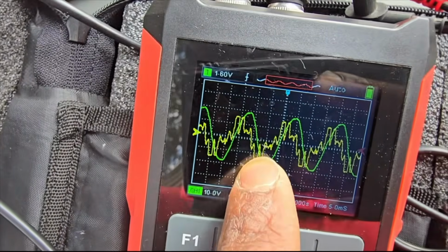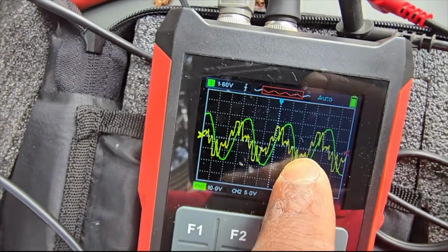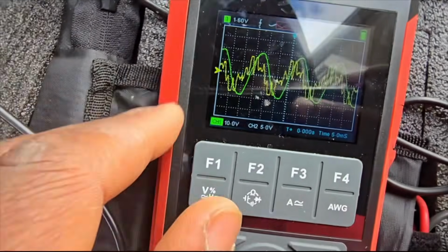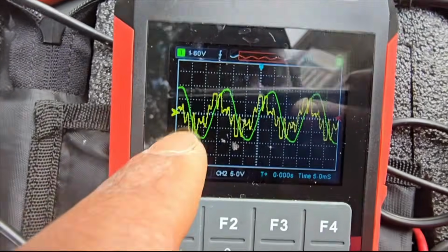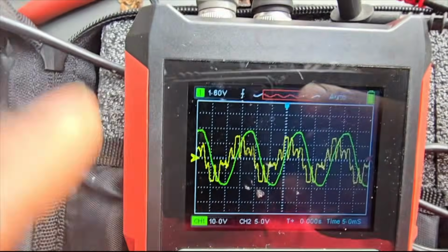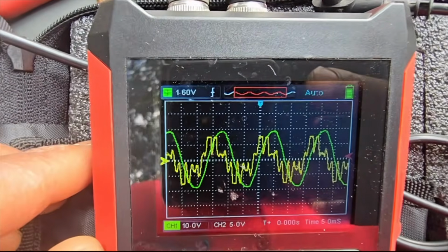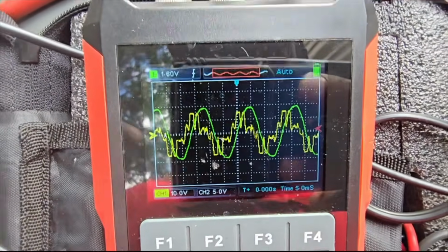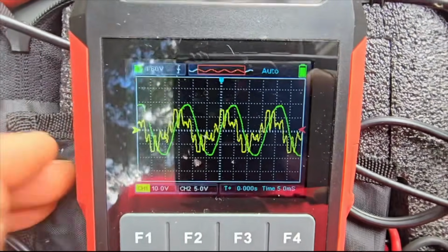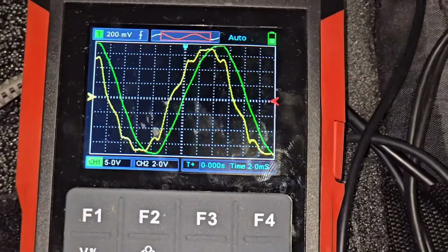I think it's really cool that you can actually verify harmonic distortion both on voltage and on your current. So if that green sine wave looked the same as this yellow one, really ridgy and distorted like that, then that would mean you had a lot of harmonic distortion on your voltage as well. As you can see, we've got a PSC motor here.